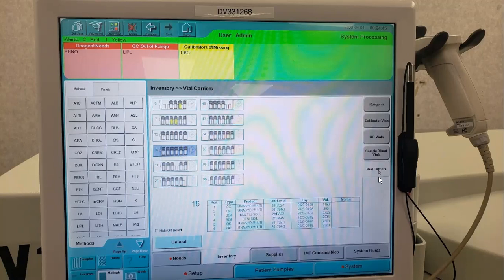What we want to check for is to make sure that all the materials that are loaded are not expired. The machine automatically will not use expired products, but it will use the ones that are very low, and even though they might only have one use, the machine will still try to run them for QC purposes. We try to avoid getting that low because if we have to run QC again, it takes a lot longer because almost all of the reagents are kept in our freezer. And it takes about 30 minutes for them to completely thaw out or more.